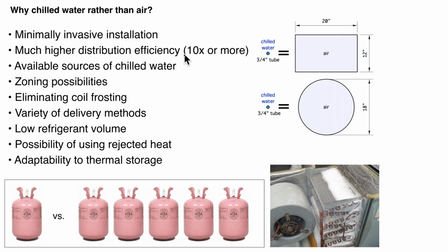Again, water, because of its high heat capacity and high density, we talk about distribution efficiency. How much energy, electrical energy, is required to move a given amount of either heating effect or cooling effect in a building. And I put down here 10x or more. A properly designed hydronic cooling system can use less than 1/10 of the electrical energy to distribute cooling through a building compared to an all air system. There's a variety of source equipment we're going to look at that can provide the chilled water. Zoning with a chilled water system is possible. It isn't something that always has to be done, but I'll compare and contrast single zone and multi-zone systems.